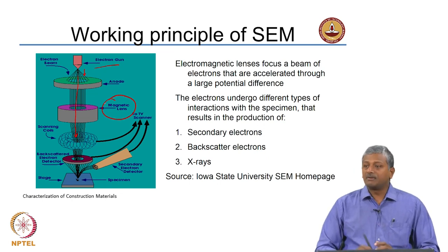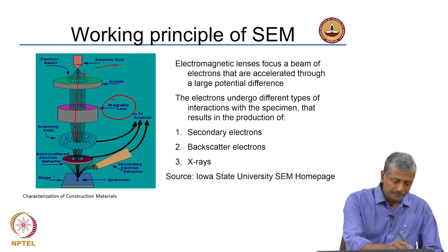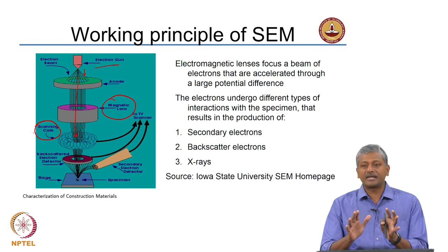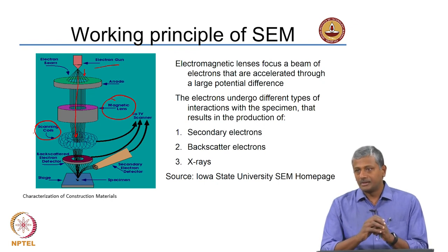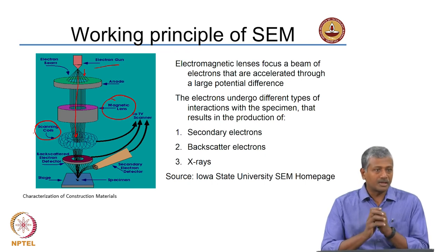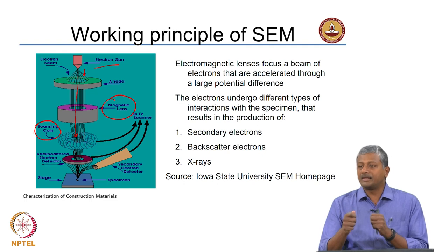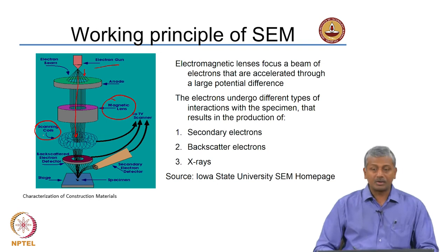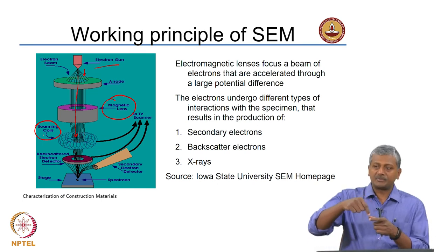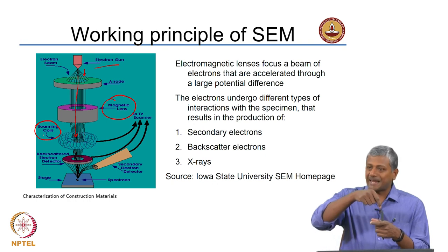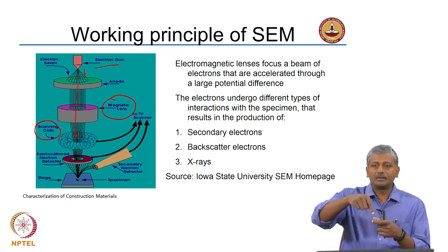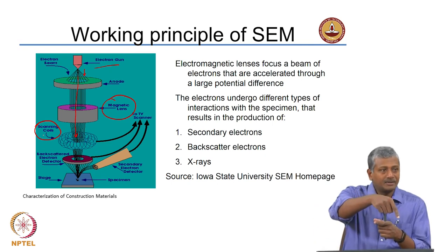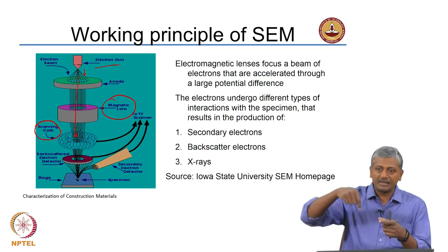After the magnetic lenses we have the objective lens system, which consists of various parts including the scanning coils. In electron microscopy, all the lenses are electromagnetic lenses — not optical lenses. The control of lens focus is done by adjusting the magnetic field generated by these lenses. The scanning coils ensure that the electron beam follows a pattern on the specimen, scanning line by line across the surface, similar to the scanning done in old cathode ray tube monitors.